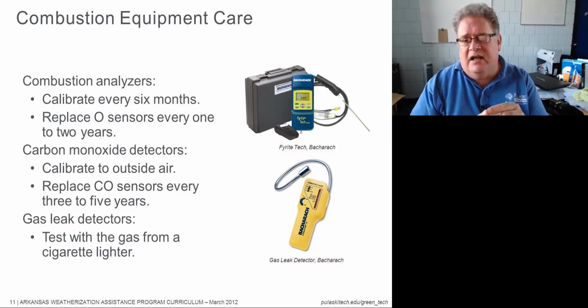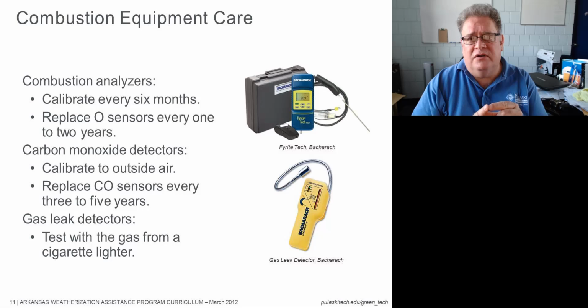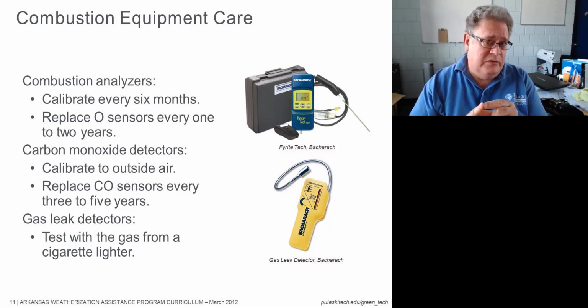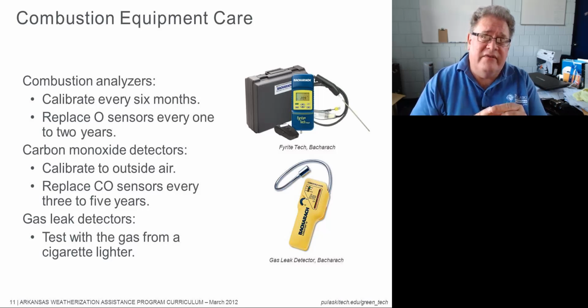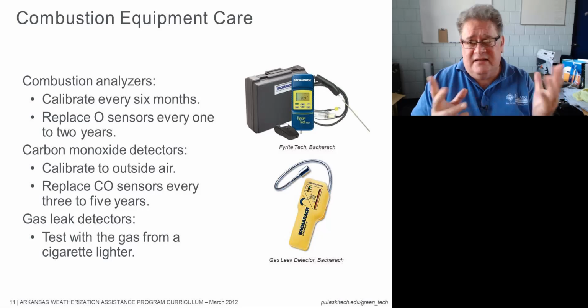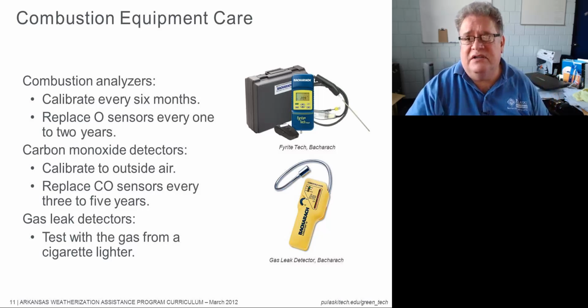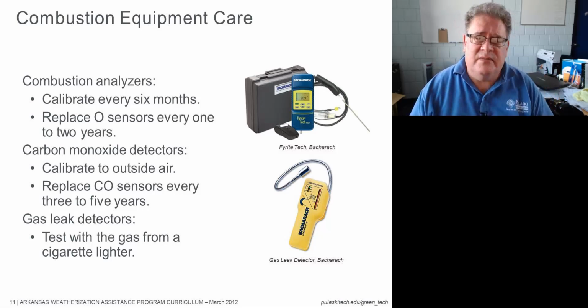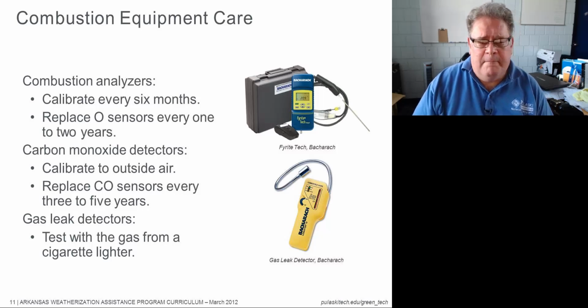But if they're not, if the unit has been exposed, if that sensor has been opened and exposed to air for a year or two, it becomes saturated even when the unit is not running. It's still coming in contact with oxygen. The reactive surface of that is degrading, which means that you're going to need a new oxygen sensor in a year or two, even if the instrument hasn't been used much.